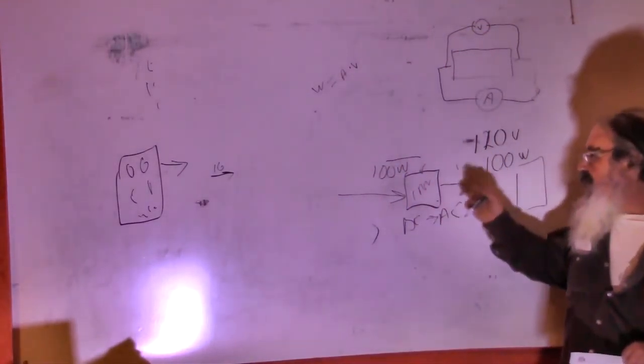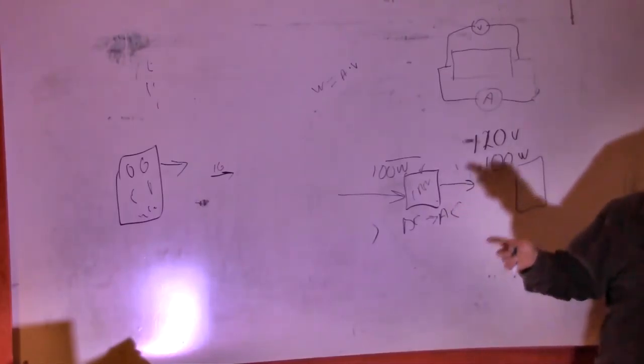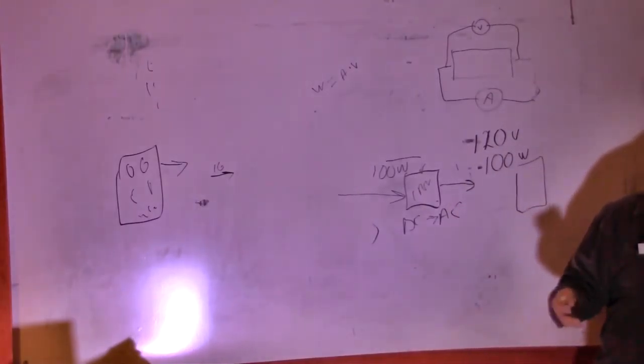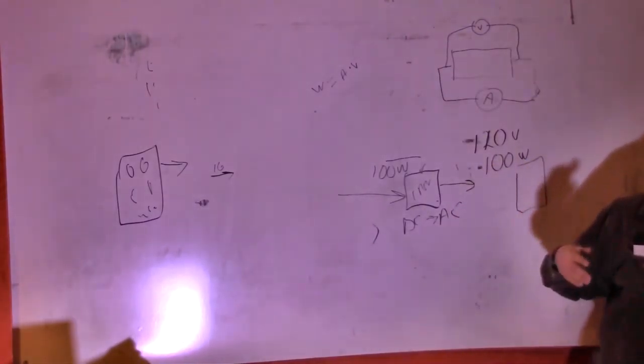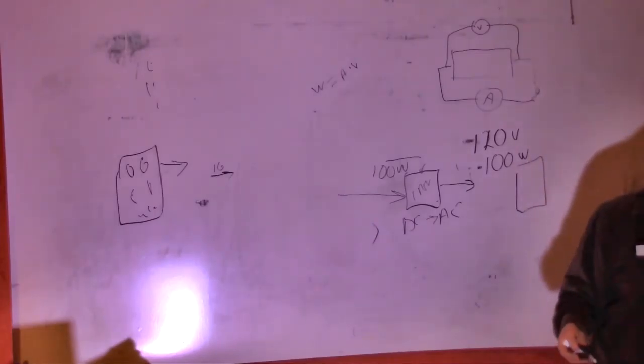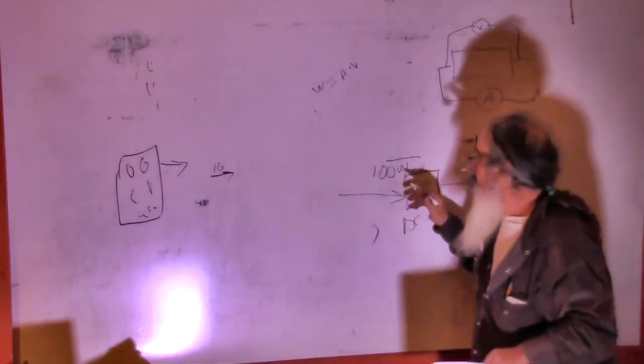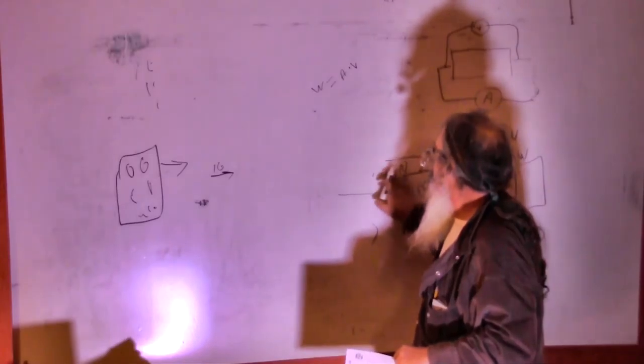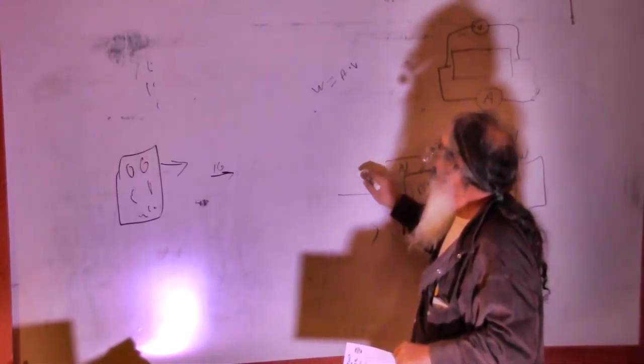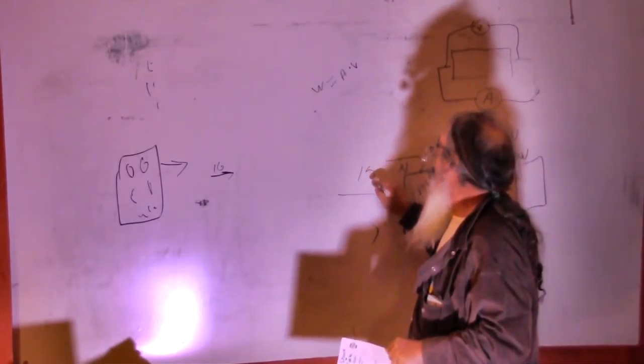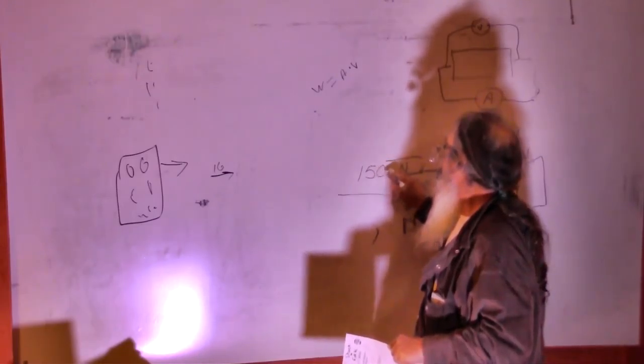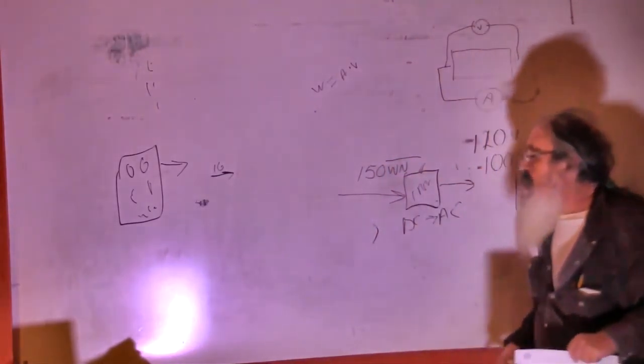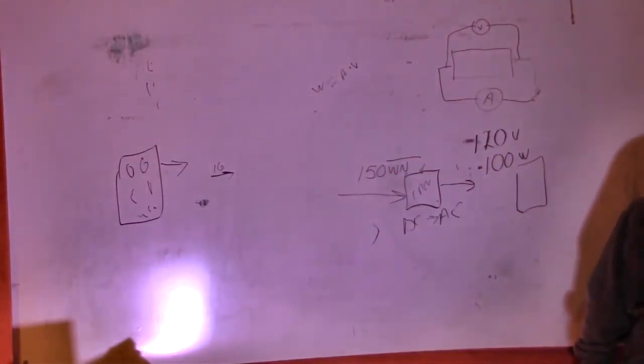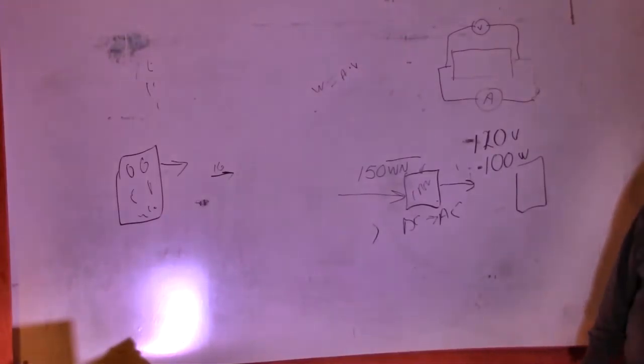And in fact, the inverter is going to lose something. Everything loses something. It's going to get hot, the fan's going to come on, and some of your electricity is going to get wasted as heat or overhead. So if it was me, I would probably go with 150 watts going into that inverter, just so you've got some slack in the system.